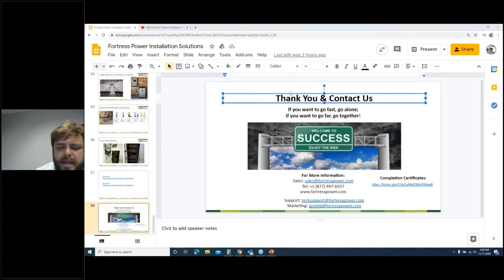For humidity, there's a couple of different things that can destroy battery life. Temperature is only one of them. Humidity and dust are the others. So when you are installing in a hot and humid environment, that's when you use the eflex, which has that IP65 rating for not allowing humidity and dust to get into the battery. In a hot operating environment, it's not so bad.